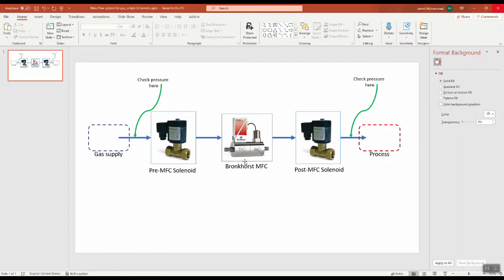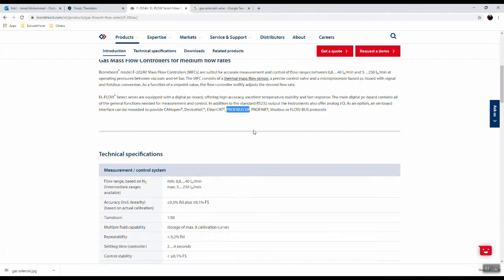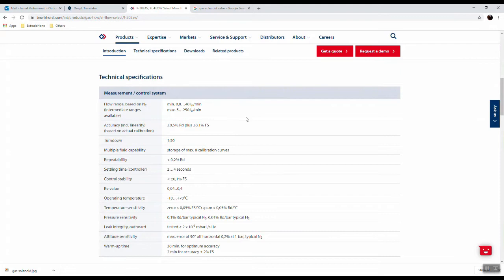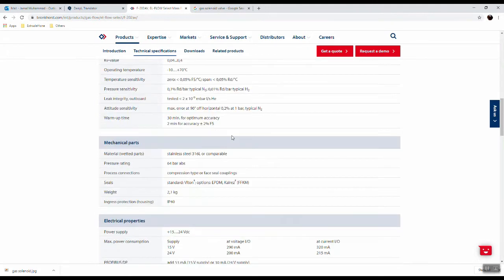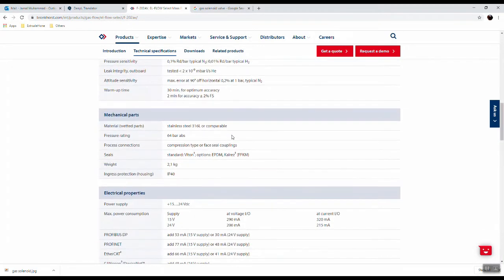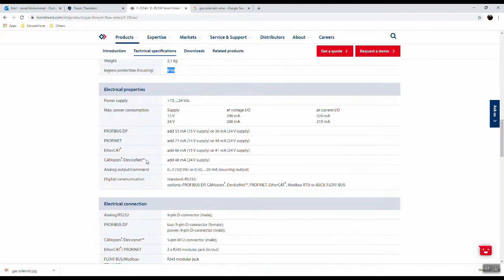Let's have a more detailed look at the Bronkhorst MFC specifications. A key property is that this MFC supports different fieldbus interfaces to communicate with the controller or PLC: CANopen, EtherCAT, PROFIBUS DP, and PROFINET. The mass flow range is 0.8 to 250 liters per minute, the temperature range is -10 to 70 degrees Celsius, and it is IP40 rated.